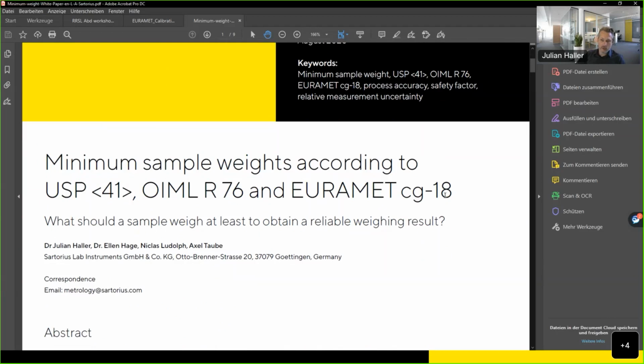Maybe just to add that for explanation, in Europe we have a clear separation between legal metrology and non-regulated devices. Only for particular applications do you need to have verified instruments, and then you have to follow R76 also concerning the minimum weight. That is whenever it is about money, something relevant for court decisions, or health. For any other application, you do not need verified instruments, and then this standard or recommendation simply does not apply.